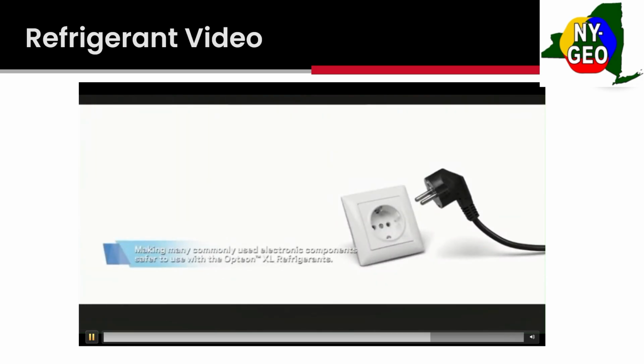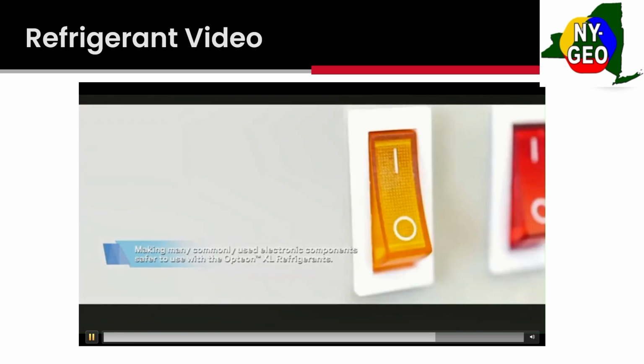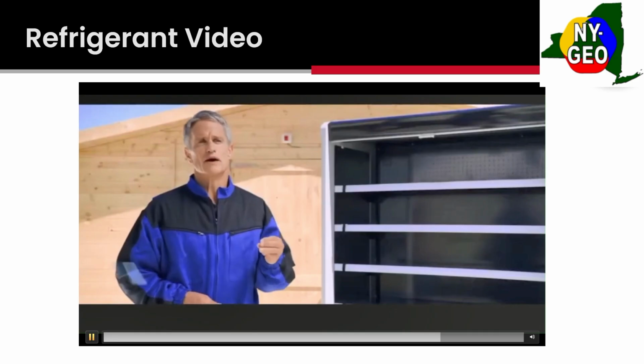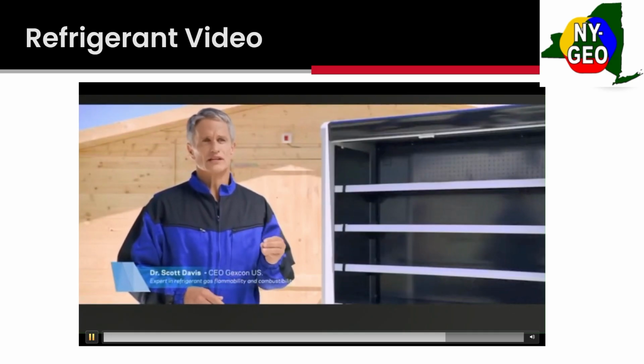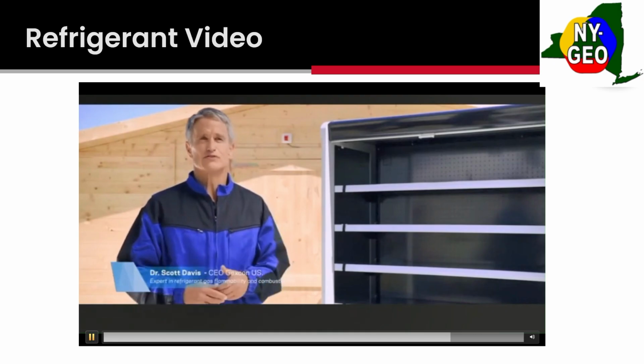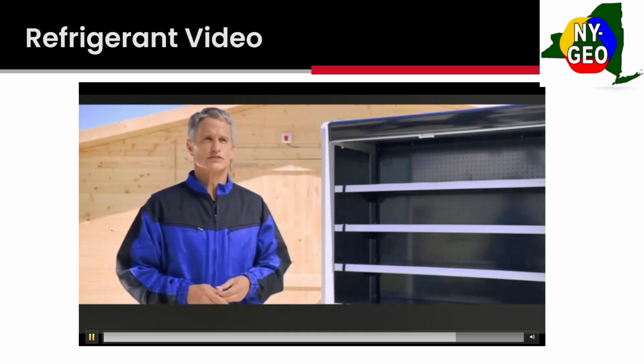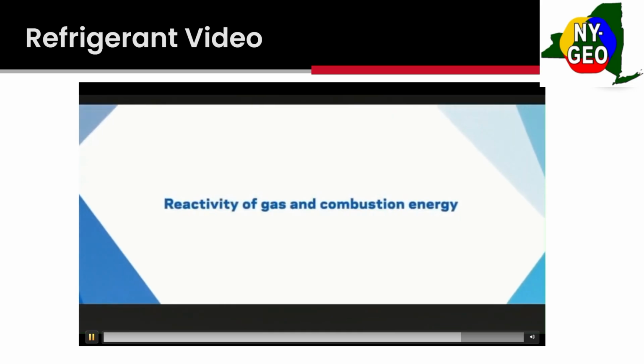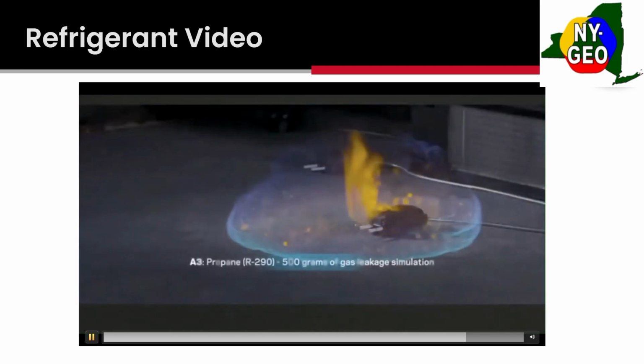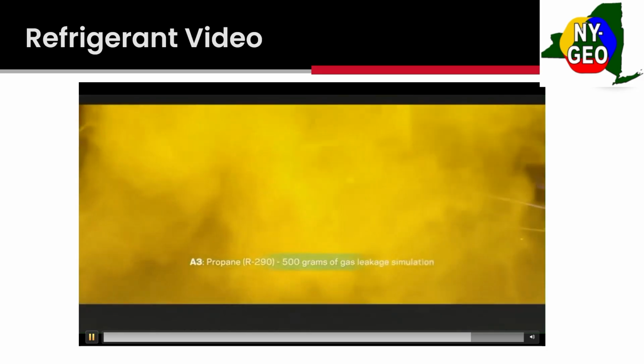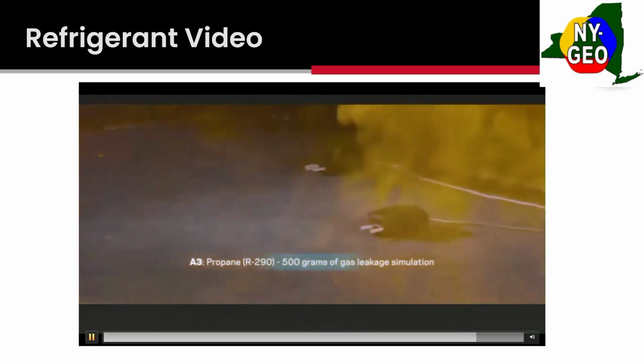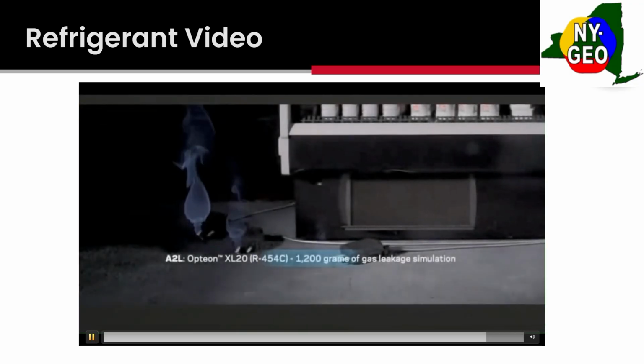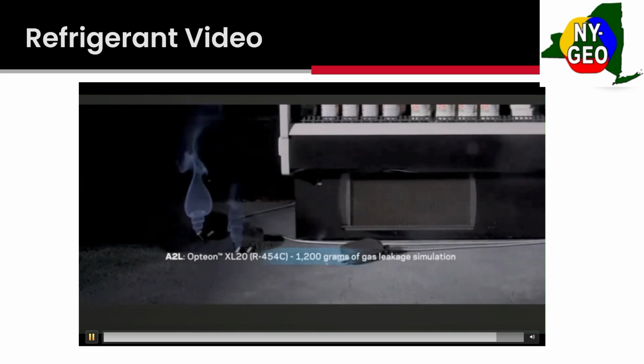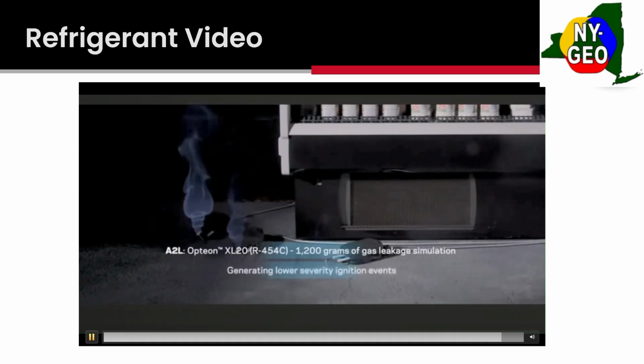The severity of an accidental ignition can be determined by many factors, such as reactivity, for example, how fast the flame burns, or burning velocity, as well as combustion energy. The higher the gas's reactivity and combustion energy, the larger the potential impact the accident can have on the surrounding area. To put that into perspective, the combustion energy of Opteon XL20 is approximately 5 times lower than that of propane. In addition, it's significantly less reactive than propane, where its burning velocity is actually 30 times slower.